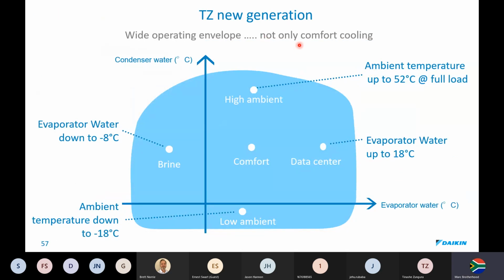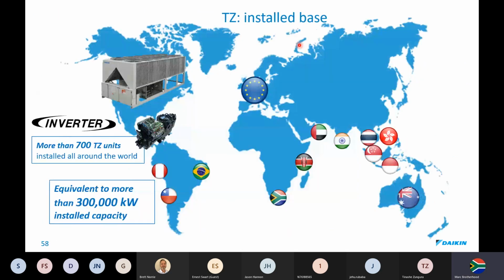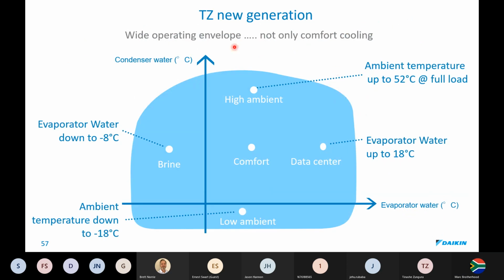So on our inverter chillers, if we look at these quadrants, ambient temperatures, we can still condense at 52-degree outdoor temperature. Evaporating water, we can go up to 18 degrees supply for data centers. As I said, you don't want to go too cold in a data center. You're going to have too much dehumidification. And here's the sweet spot for comfort cooling. We can go down to minus 18 degrees outdoor temperature. We can still provide cooling for you.